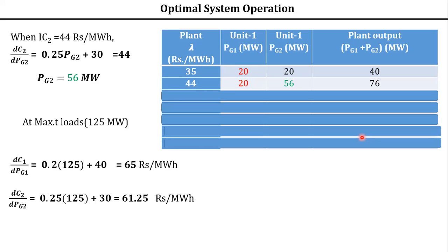At 61.25, Sumant has given the answer: loading on unit 1 is 106.25 megawatt and loading on unit 2 will be 125 megawatt. And at 65, the loading on unit 1 will be 125, unit 2 will be 140. Here, Sumant, you have made a mistake. The first one at 61.25 is okay. Now I'm going to explain before showing the values. At 61.25, unit 2...